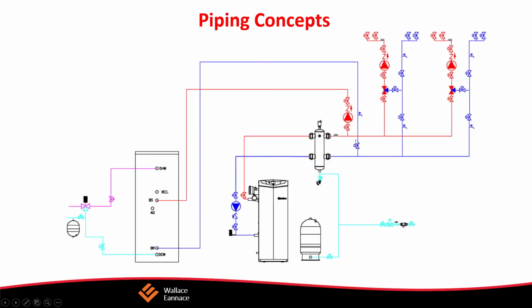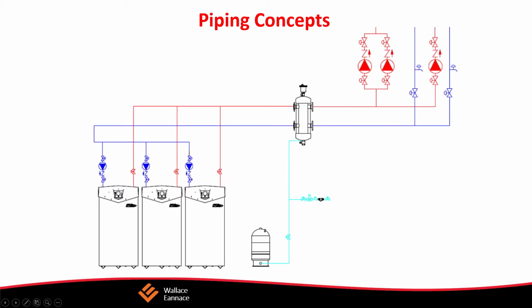Here you can see that you have a regular T on one end, the flow splits, and then the restriction here creates a pressure drop, and the water comes back in and flows through the radiator. Another method is a two-pipe direct return system. This is going to use more pipe, so it's more expensive. It's much easier to zone. The delta T will vary, and you may not get equal flow in the radiators.